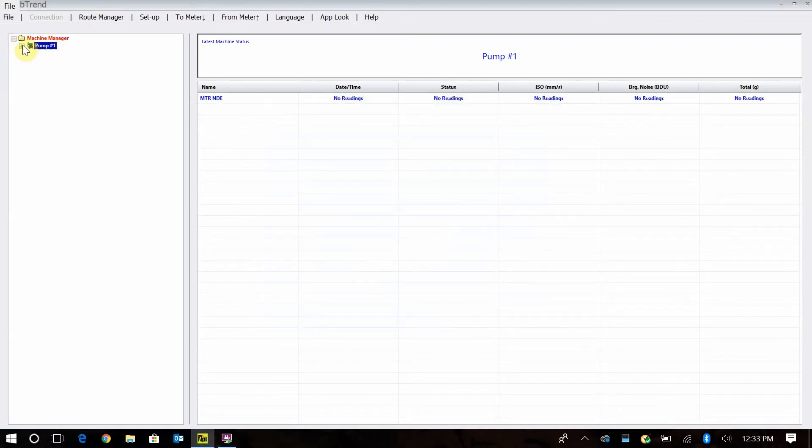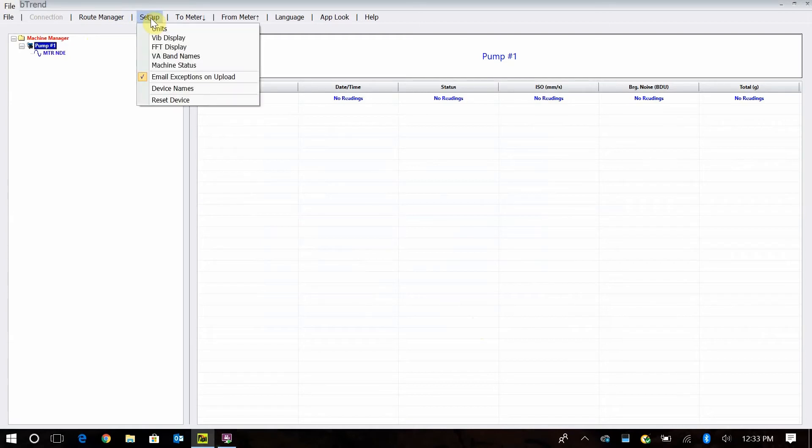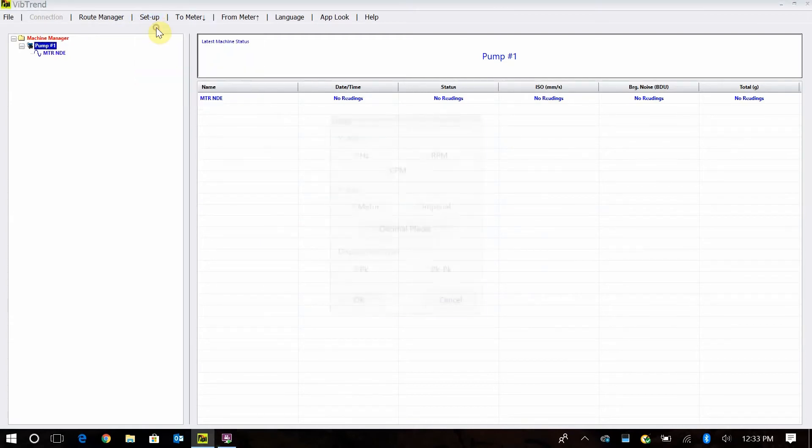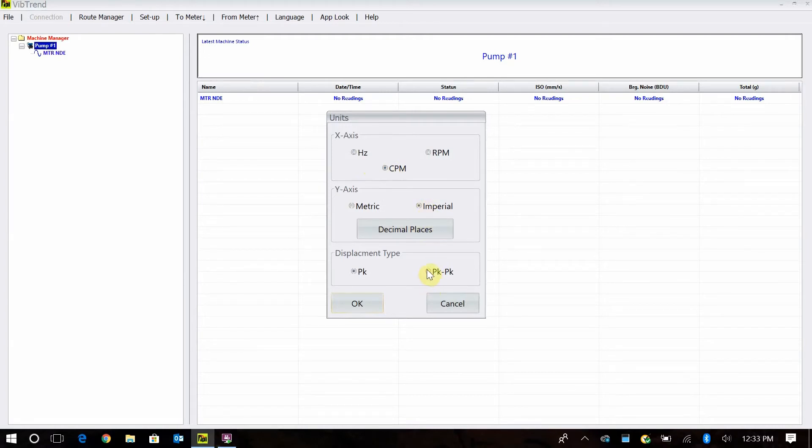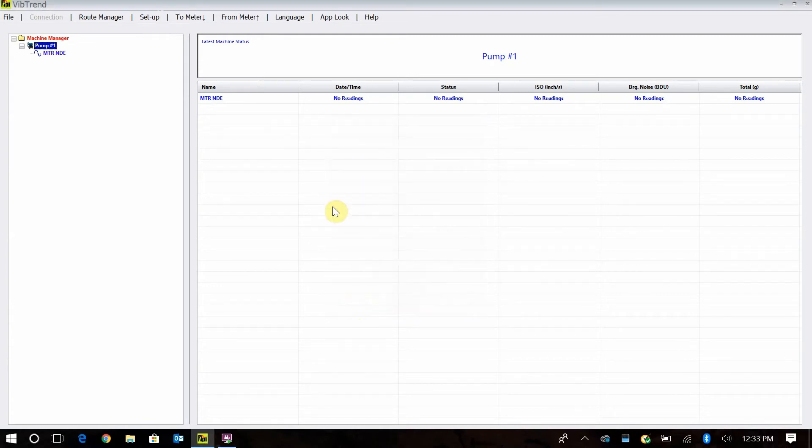I'm going to show you, you saw everything was in millimeters per second. If you want to see things in inches per second, you just go up to your setup point right here and then your units. This is where you set everything. I'm going to set everything to cycles per minute and imperial units. And then my displacement, I want in peak to peak and I tell it OK. Now when I'm doing my setup, I'll see everything in inches per second.